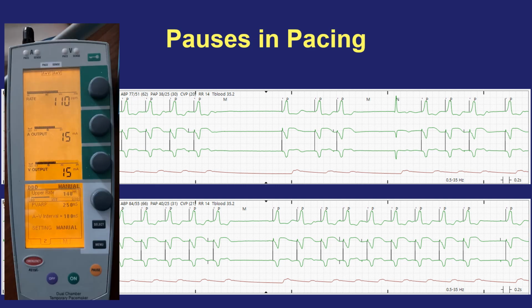There are a couple of ways that this can be quickly managed. The easiest way actually is to find the emergency button here, which turns the pacing mode to asynchronous. It says it in really small type here, but async means that it will change the pacing mode to an asynchronous mode, that's VOO or DOO. That can also be done manually. If you go into the menu in the bottom part of this type of pacemaker box, you can find, in this case, the dial mode, switching the DDD or VVI to DOO. That would do the same thing as switching to async.